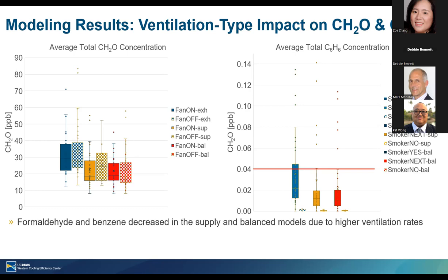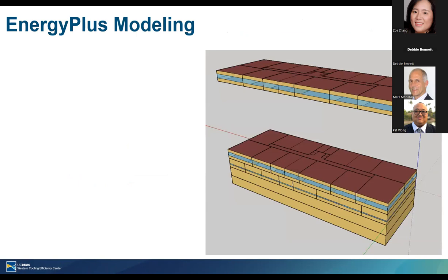For formaldehyde and benzene by ventilation type: formaldehyde concentrations are driven by ventilation rate, so since supply and balanced systems have higher ventilation rates, they show lower concentration distributions than exhaust-only systems. When looking at concentration being transferred from neighboring units, the exhaust system has slightly higher transfer, while both supply and balanced have less inter-unit transfer. Now switching to the EnergyPlus building model.